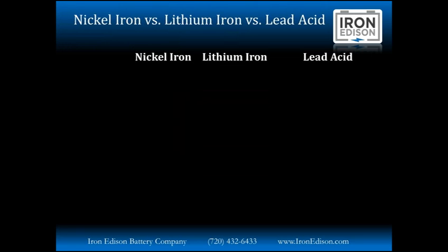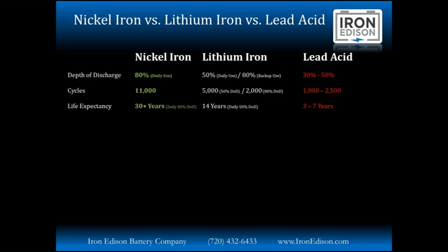So now we've given you an overview of nickel iron and lithium iron batteries. Let's do a side-by-side comparison so you can see the pros and the cons of nickel iron and lithium iron, especially compared to lead acid batteries. First of all, the depth of discharge and life cycle expectancy. Nickel iron really shines in this category. We can do 80% depth of discharge on a nickel iron battery, and we're not going to negatively impact the life expectancy. That's just one of the positive characteristics of the nickel iron chemistry. So doing a daily 80% depth of discharge, you can see 11,000 cycles out of the life of a nickel iron battery. Doing that daily, that's 30 plus years of life.